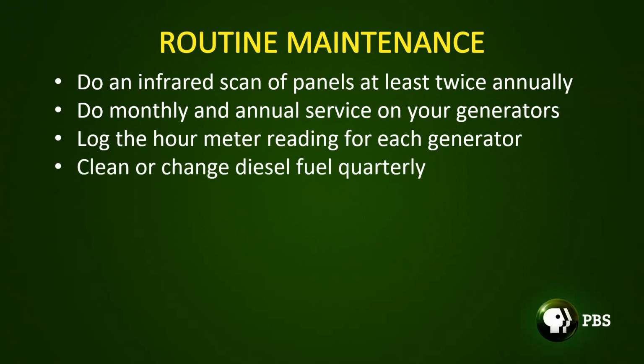Another one is to clean or change your diesel fuel quarterly. This is probably overkill, but it's what we have to do here because our environment isn't particularly friendly, even though we use an underground tank. There are services, and most can be provided by your fuel provider, where they come and pump out the fuel from your tank and replace it. What do they do with the old fuel? They take it back, filter it, and resell it. So it's a way to keep from getting into a situation where you have a lot of sediment, water, or other pollutants in your fuel.